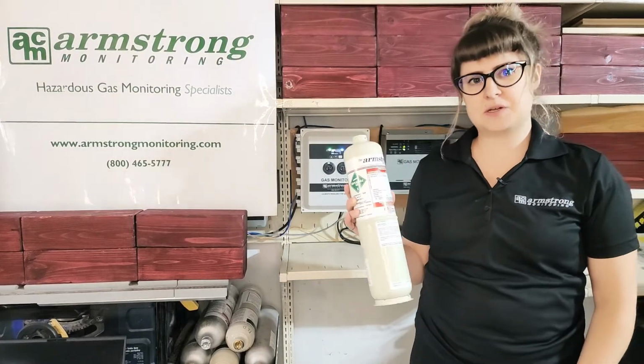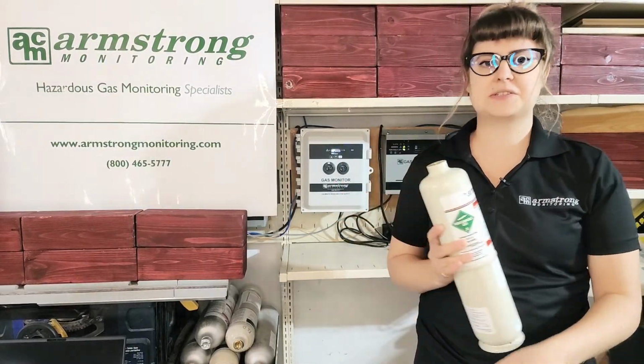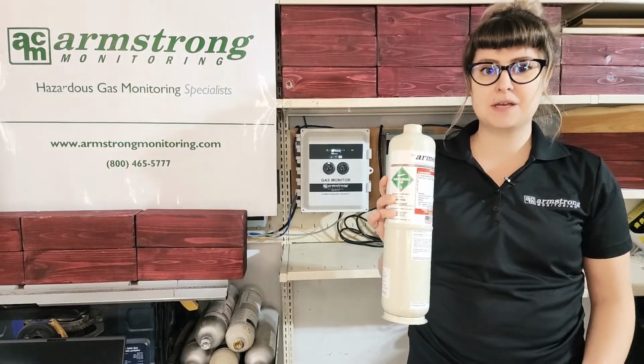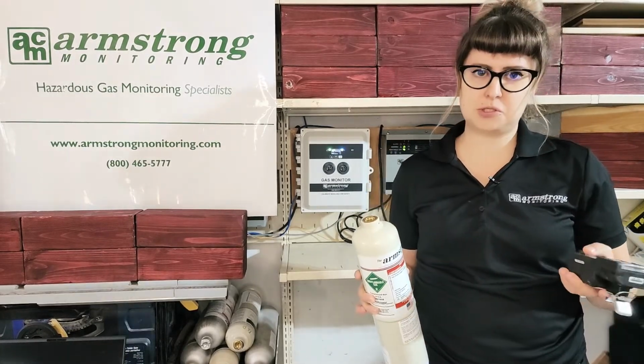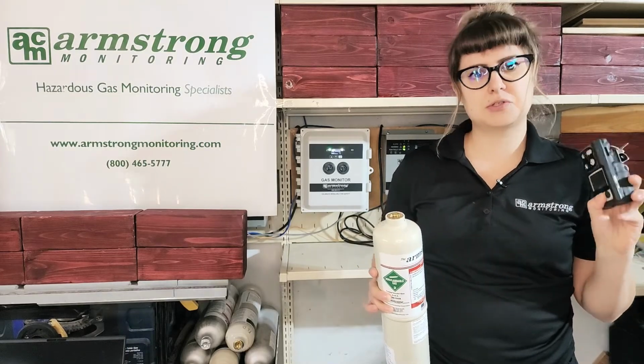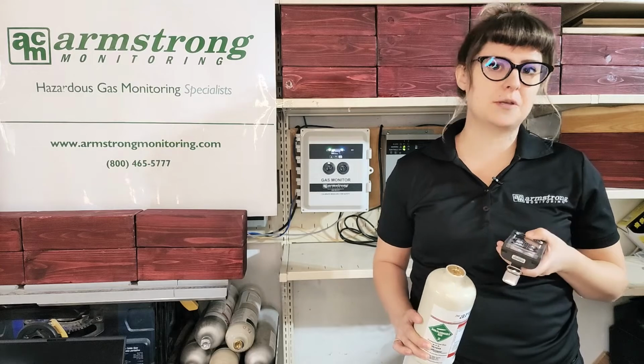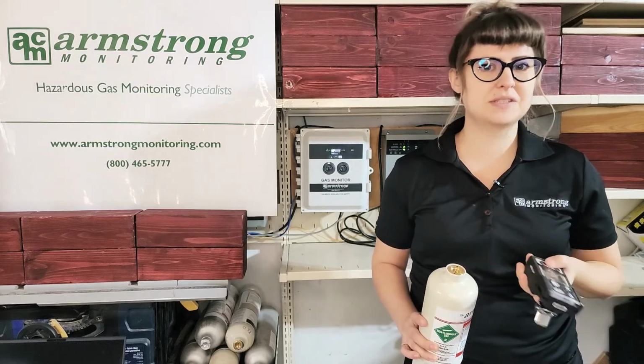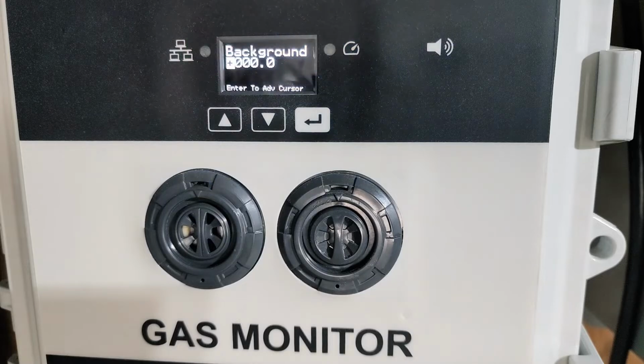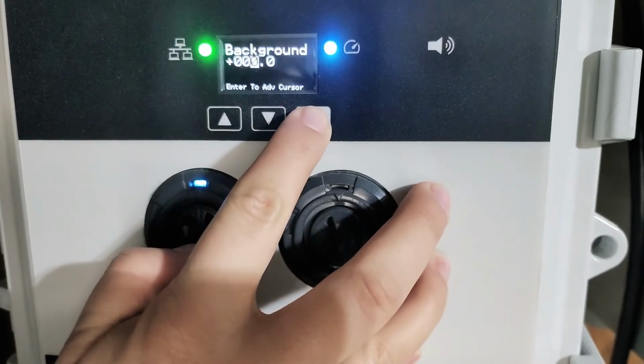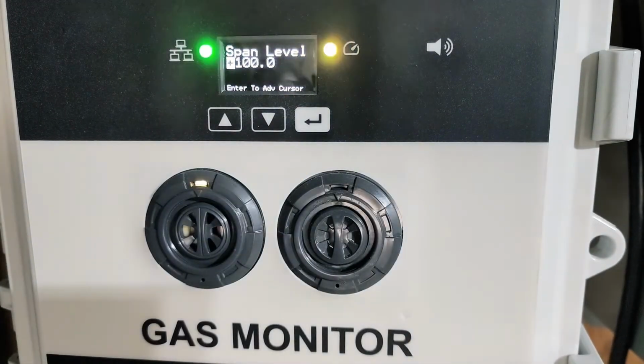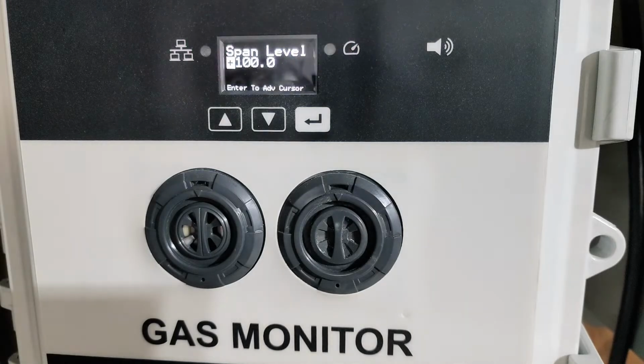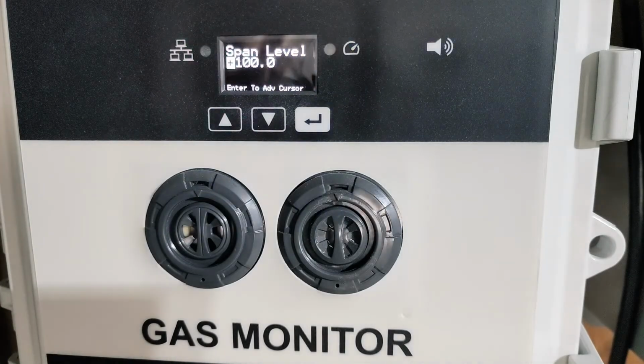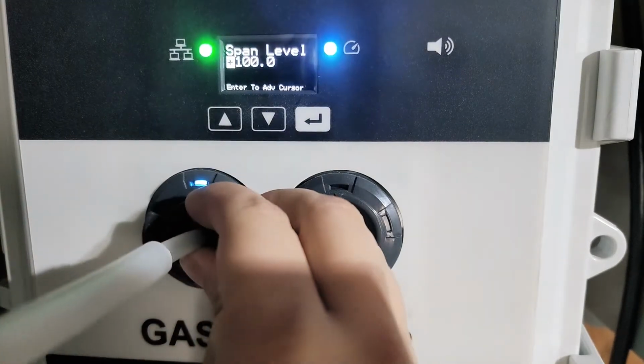I'll first start by demonstrating the method using pure nitrogen to apply to the device during the zero calibration step. And then I'll move on to demonstrating the second option, which uses the portable device. It's important to ensure that your portable has been calibrated recently for the best results, and we recommend once every 6 months. For the first option, when prompted to enter the background concentration, select 0, open your nitrogen calibration cylinder, and then apply the calibration adapter to the sensor module so that it is ready for the find zero step.